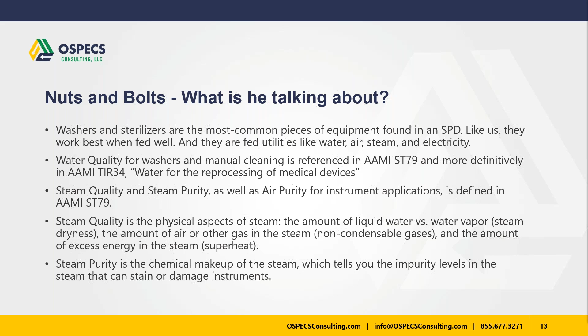And the purity is the chemical makeup of the steam, and there are allowable contaminant levels that you really shouldn't go past. Steris Laboratories does a good job on that. I fill in certain blanks when I do my testing, but there is a lot to be looked at just to make sure that things can happen in a reliable manner. On the next slide, please.